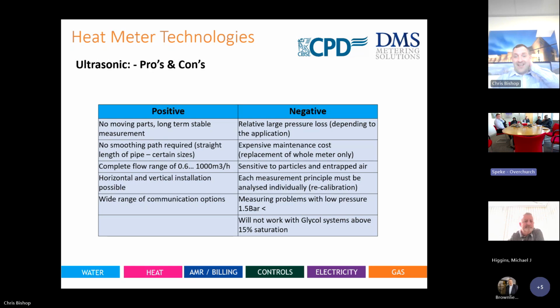Each measurement principle must be analysed individually. So the recalibration method, and this is where it's not fully accepted in the UK yet, but it's a conversation, is all meters would have to be taken out of the application and sent back to point of manufacture. But it can't be an on-site conversation at the moment. Quite costly. There's no legislation for that yet, but I think with how the district heating regulations are going, there's going to have to be. So this is still a bit of touchy ground moving forward. With ultrasonics at the moment, it's take out, send back to point of manufacture. It would work out cheaper just to replace the meter, strangely enough. Yeah.